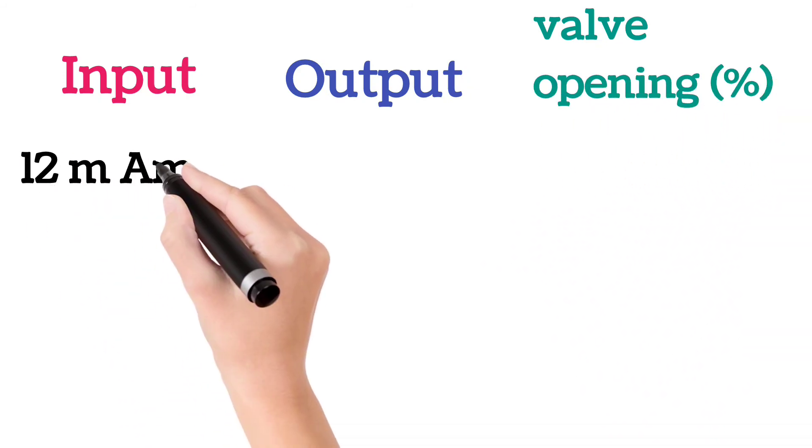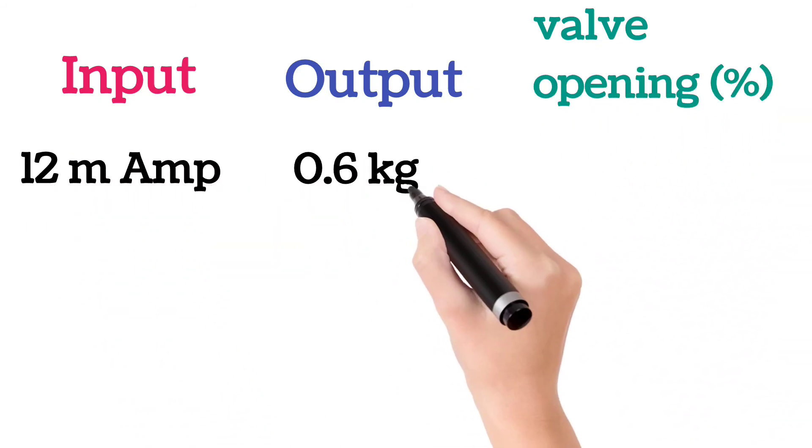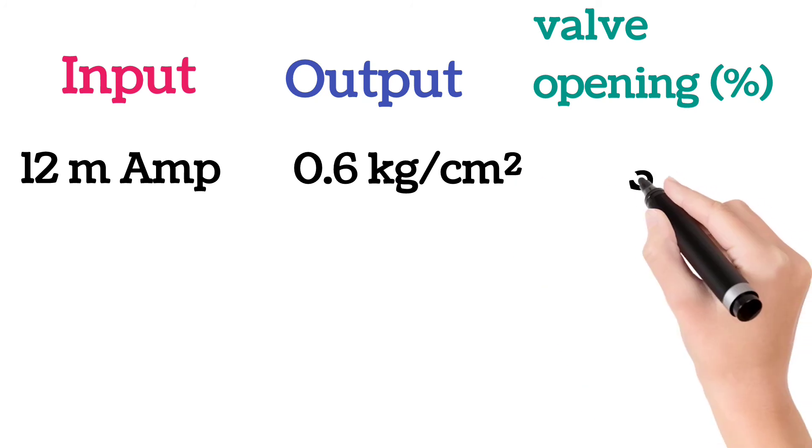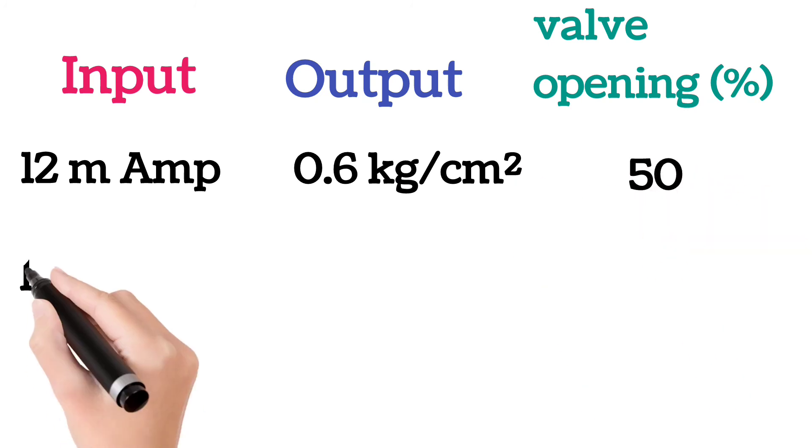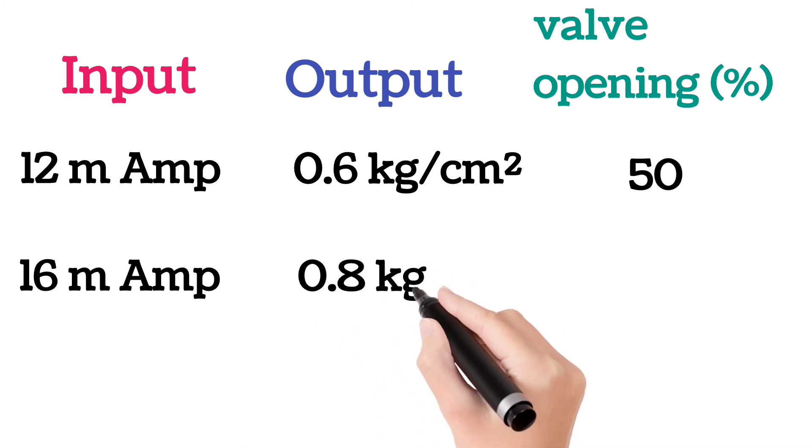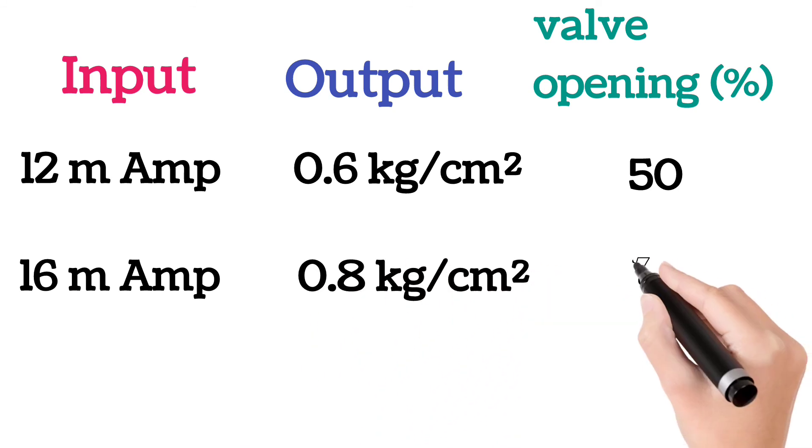at 12 milliamps, its output is 0.6 kg per square centimeter and valve opening is 50%. At 16 milliamps, output is 0.8 and valve opening is 75%.